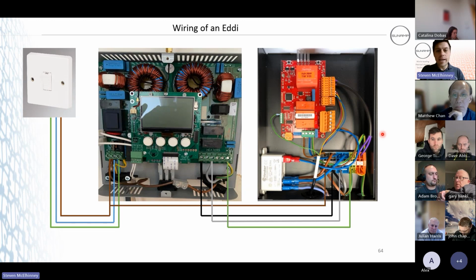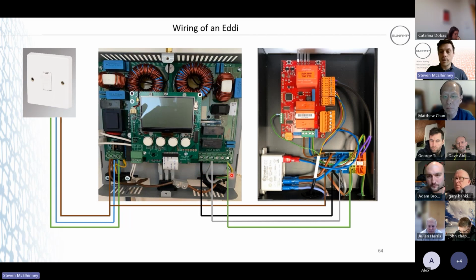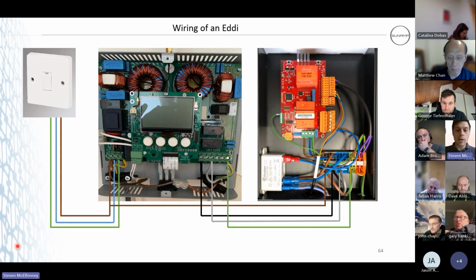But the wiring of your Eddi, for example, you've got obviously power coming in, permanent live, which powers up your Eddi. We piggyback off that. So again, if you think about our 4-core flex, your brown is tying into the permanent live of your incoming supply, the Eddi. And your black, which is your switch live, goes into heater 1, your neutral goes into neutral 1, and then earth obviously goes into earth. And that's how you wire it up. So that's the wiring of your Eddi. So just remember, we get a lot of issues where installers have put the brown, the black, the neutral, and it just doesn't work.